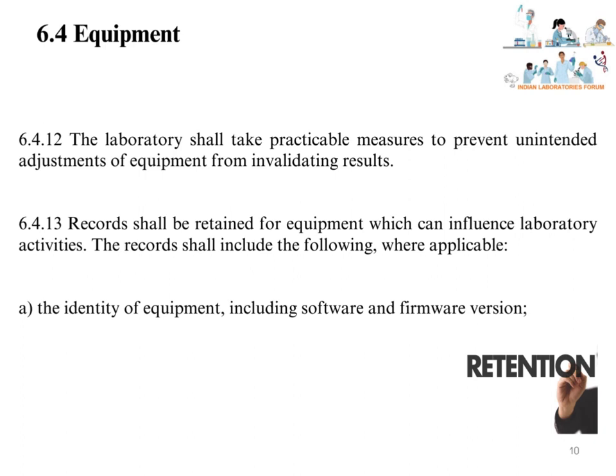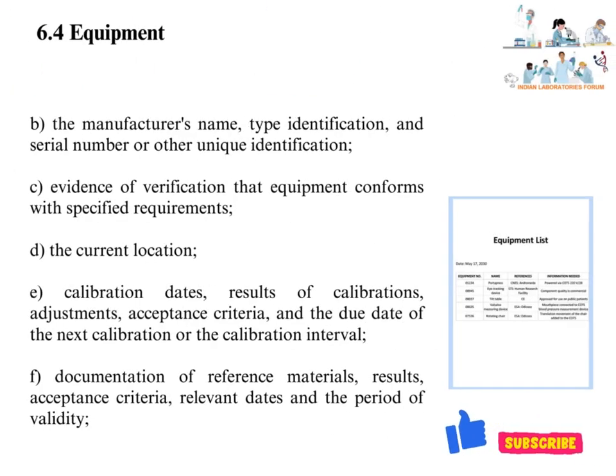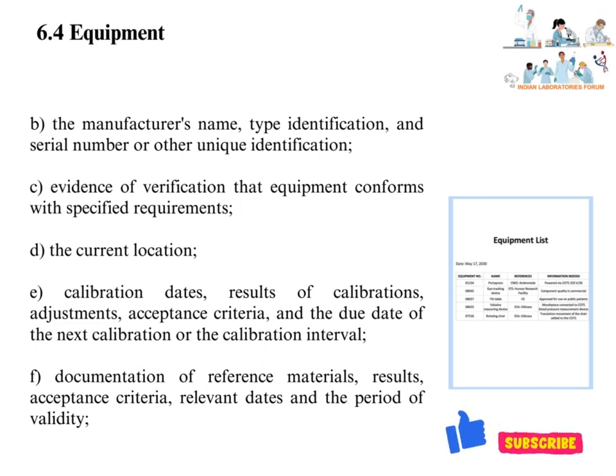Records shall be retained for equipment which can influence laboratory activities. Records shall include: the identity of equipment including software and firmware version; the manufacturer's name, type identification, and serial number or other unique identification — generally covered in a master list of equipment; and evidence of verification that equipment conforms with specified requirements, meaning IQ, OQ, and PQ data and records.